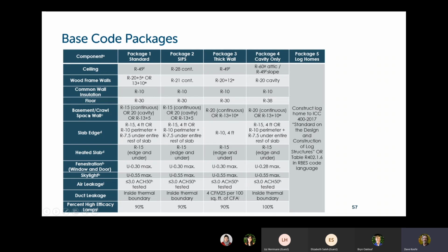This is your basement or crawl space wall, R15 continuous or R20 cavity. There's the slab edge insulation. It's the same numbers I mentioned early on, with that 4-foot idea that the insulation is either 4 feet high or a combination of vertical and horizontal that adds up to 4 feet. Then you have the heated slab, which is if you have a radiant slab, there's your windows, your skylights, your air tightness, which is the same for everybody, and your duct leakage, which in package 2 and package 4 is all inside the thermal boundary. In package 3, you are allowed to have some duct leakage to outdoors, but of course you're going to have to test for that. And then percent high efficacy lamps.